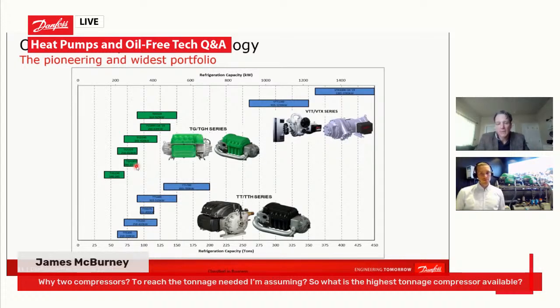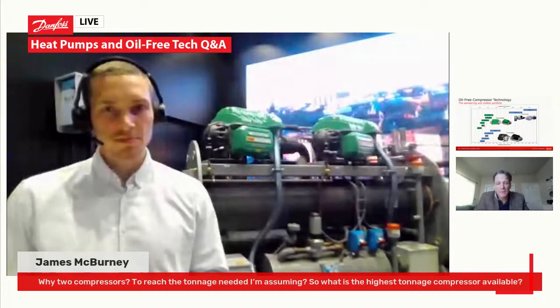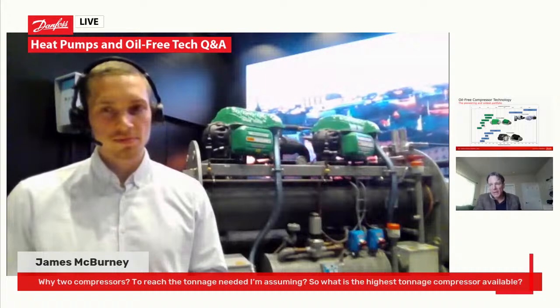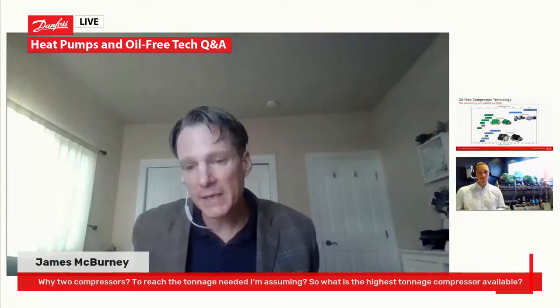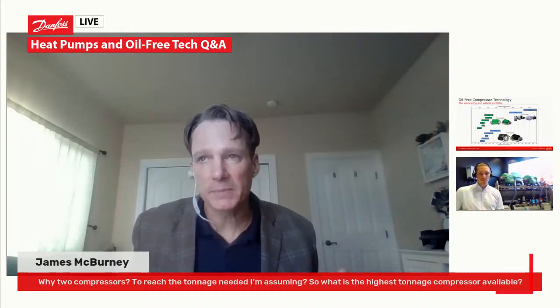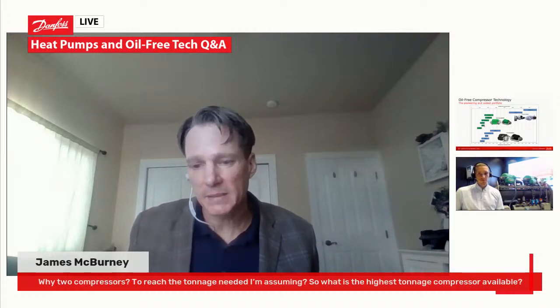But to the system design, the one that Jonas is standing in front of, the reason two compressors are used on that system is that one of the primary benefits with Turbocor is that you can manifold as many compressors as you want on a single circuit. We've seen the same manufacturer who built that chiller behind him apply chillers with up to 12 compressors. What enables that is the oil-free operation, because the main thing that drives separating compressors into circuits is making sure you get oil back to the compressor that needs it. Without that limitation, you can manifold as many as you want. That means you can benefit from the heat exchanger scale and the approach temperature associated with multiple compressors, for example running 2 of 12 compressors on a larger heat exchanger based system design.